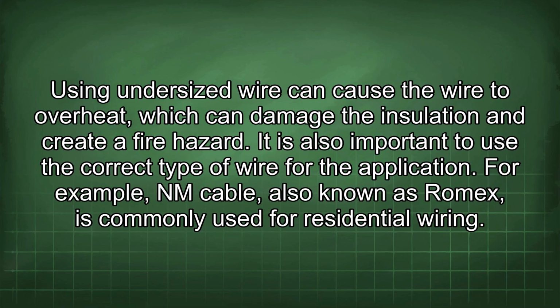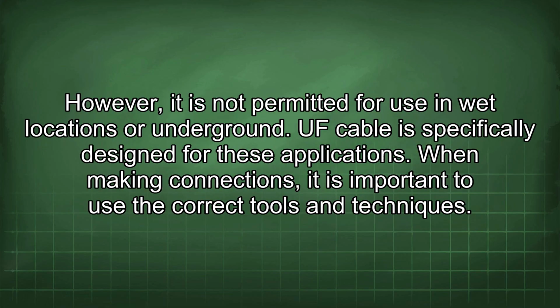It is also important to use the correct type of wire for the application. For example, NM cable, also known as Romex, is commonly used for residential wiring. However, it is not permitted for use in wet locations or underground. UF cable is specifically designed for these applications.